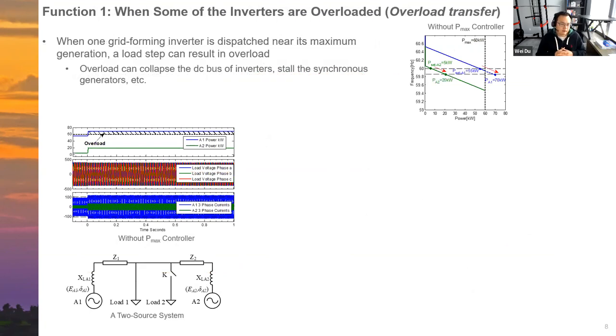Let's consider a very simple two grid forming inverter system. We have grid forming inverter A1 and grid forming inverter A2. We dispatch the output power of A1 to near its maximum at the very beginning. So at the very beginning, the output power of A1 is close to its maximum and A2 is far away from its maximum. In this case, if we switch load 2 on, we'll see that both grid forming inverter A1 and grid forming inverter A2 increase their currents almost instantaneously to meet this load change. This is just because they behave as voltage sources.